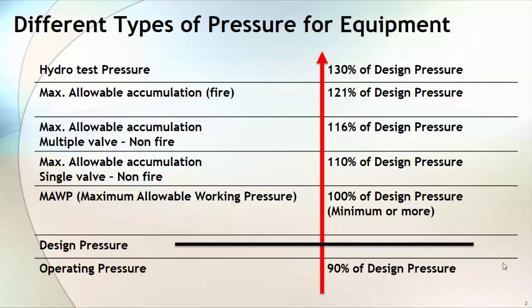Now with the help of this operating pressure, the equipment designer will add some safety margin — usually in the range of 10 to 25%, depending on the experience of the designer. He will consider unusual events that may occur during normal operation, and based on this he will come up with some design pressure number.